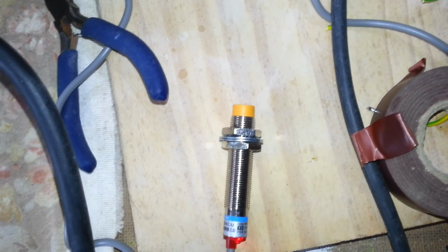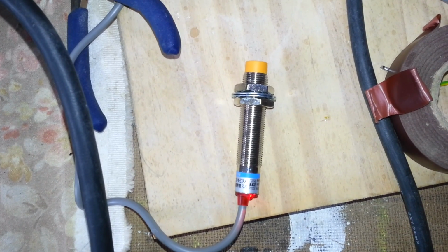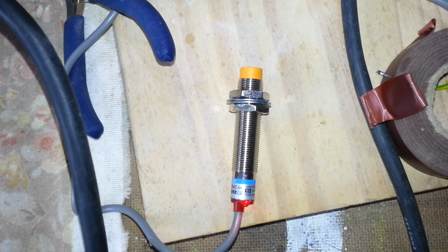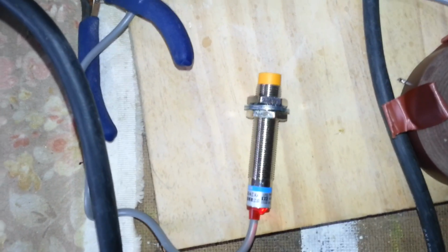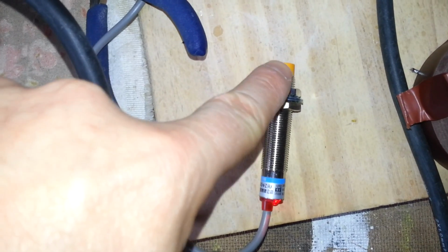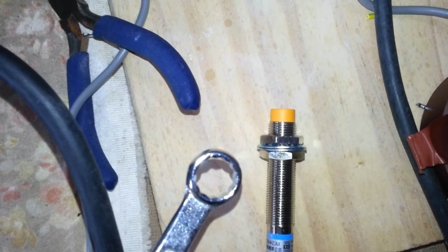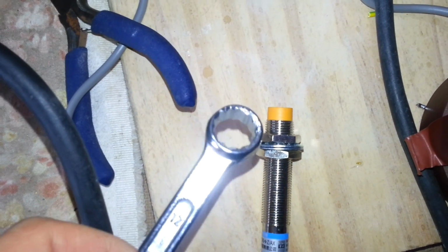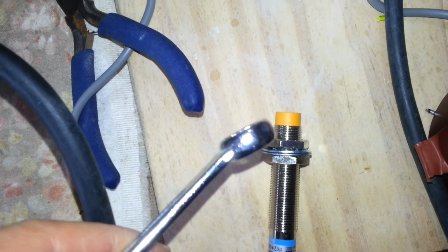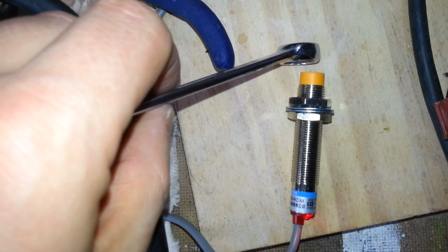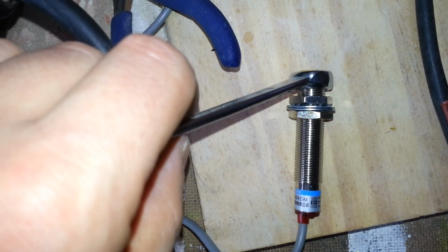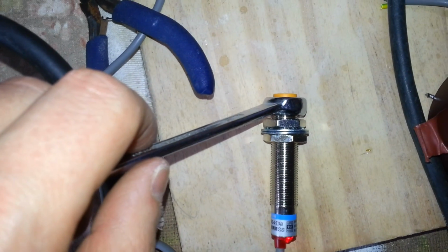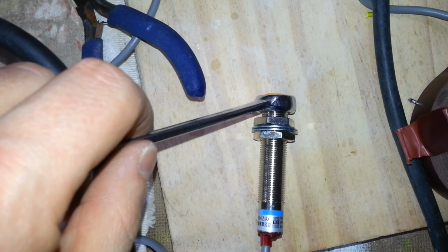But one of the things with these sensors is they come in two types. You can get flush mount or protruding. Flush mount tend to be a little bit more expensive because they have to shield around the top of the sensor. Now, I don't know what type these are, so I thought I'd do a quick little test. What I thought was, if I use a spanner that goes over the head, then that will act just like a case. If it was flush mounted, you should be able to get the head of the spanner. Obviously it's going to trigger there, but when the spanner comes down, it shouldn't trigger.